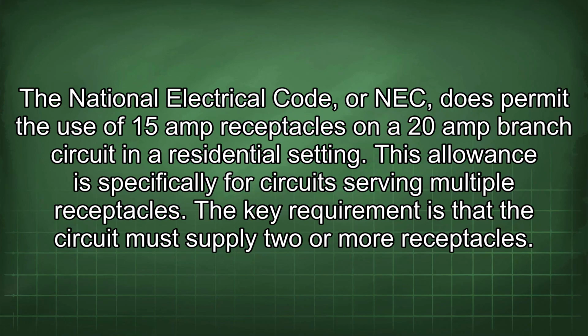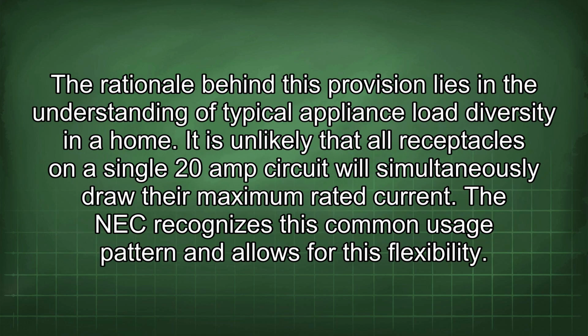National Electrical Code, or NEC, does permit the use of 15-amp receptacles on a 20-amp branch circuit in a residential setting. This allowance is specifically for circuits serving multiple receptacles. The key requirement is that the circuit must supply 2 or more receptacles. The rationale behind this provision lies in the understanding of typical appliance load diversity in a home.